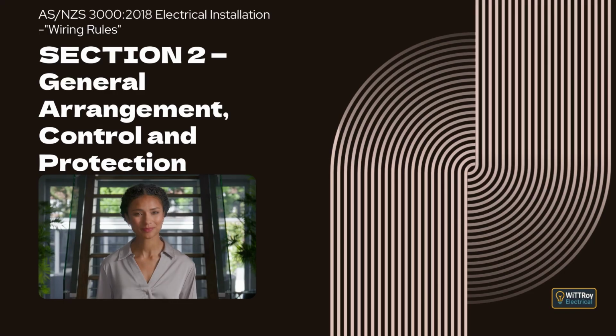For main switches in an outbuilding, the rule is that the main switch or isolating switch must be installed on the switchboard inside the outbuilding. This gives anyone working in the outbuilding a safe way to isolate the supply without going back to the main building. If the outbuilding is supplied by more than one submain, each submain must have its own main switch. Those switches do not need to be mounted side by side, but there must be a clear notice showing where all the other main switches for that outbuilding are located. This helps anyone working in the outbuilding isolate every supply safely.